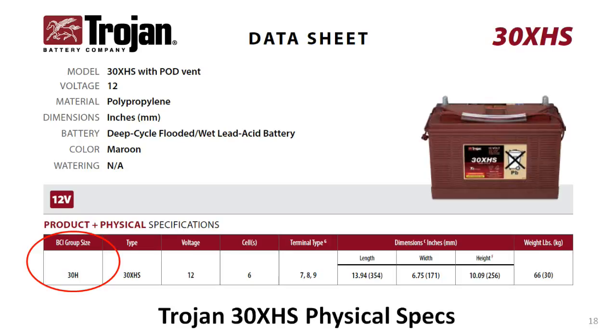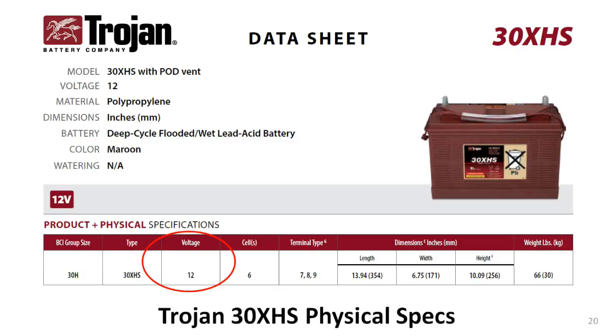The first column in the table refers to the battery's size and shape. There are standardized dimensions defined by the Battery Council International, abbreviated BCI. Some of the most common sizes are called Group 24, Group 27, Group 31, and so forth. The 30XHS battery conforms to the dimensions for a Group 30H. The second column is labeled type but really should be labeled model, as 30XHS is a Trojan model number. The third column repeats the voltage — 12 volts — and column four tells you there are six individual cells inside the case, which is standard for a 12-volt lead-acid battery.